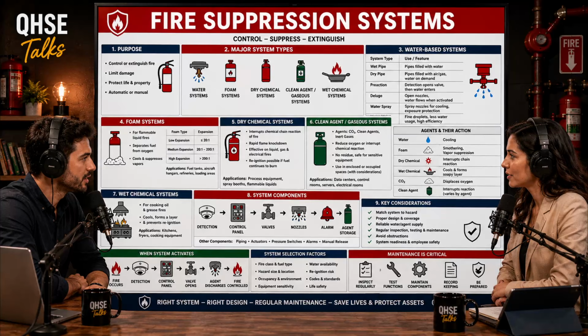Yeah, precisely. They alter their response strategy immediately. Second, you must minimize the downtime by scheduling work during off hours. And third, you must implement alternative protections, like a continuous fire watch, where trained personnel patrol the area with extinguishers. Yes. Their sole job is to watch for sparks or smoke and suppress a fire instantly.